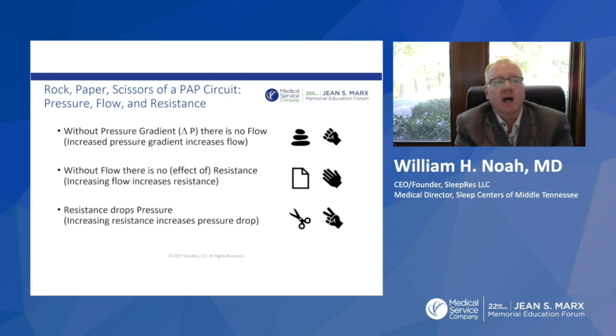Without a pressure gradient, there is no flow. Flow does not exist on its own. Without flow, there is no effective resistance. You can have a resistor in your circuit, but if there's no flow across it, there's no drop in pressure, no effect of the resistance. So flow doesn't create the resistance, but flow creates the effect of the resistance. If you increase flow, you increase the resistance, or the pressure drop. This resistance drops pressure. Everyone thinks resistance decreases flow, but it decreases the pressure gradient, and resistance drops pressure. So for rock, paper, scissors, you've got pressure takes flow, flow takes resistance, and resistance takes pressure.